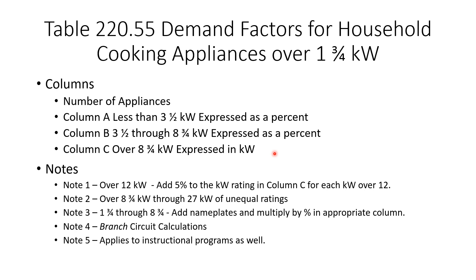The table has several notes that can be intimidating, so let's take them one at a time. Note 1: if you're dealing with over 12 kilowatts — up to 27 kilowatts — you're going to add 5 percent to the kilowatt rating in Column C for each kilowatt over 12.